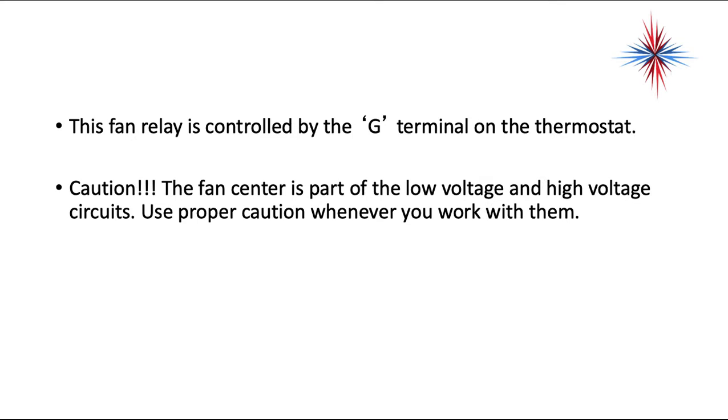The fan relay is controlled by the G terminal on the thermostat. Now, there's a little note of caution here. The fan center is part of the low voltage and high voltage circuits. You have to make sure you use proper caution whenever you work with them. High voltage is not very forgiving and low voltage will blow out a transformer if you wire it incorrectly.